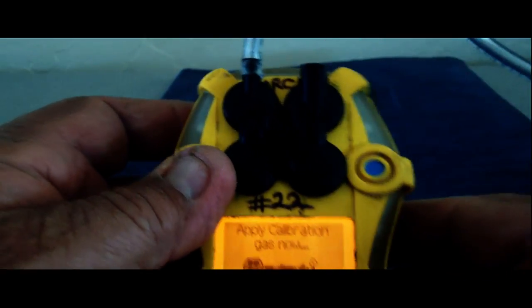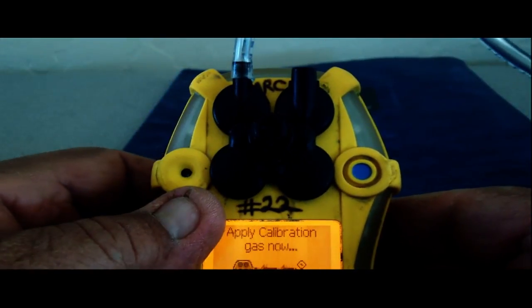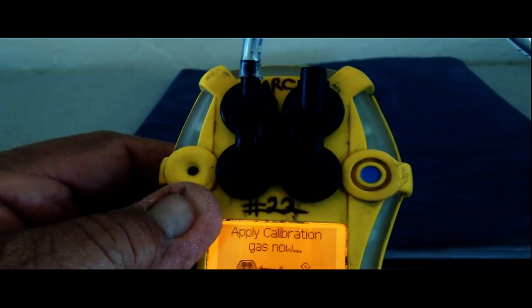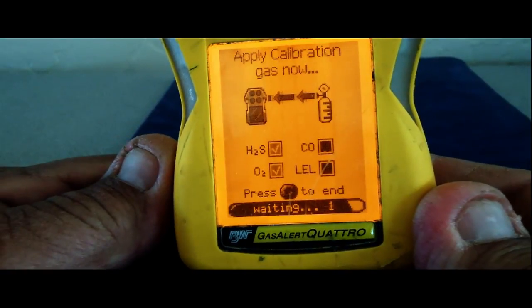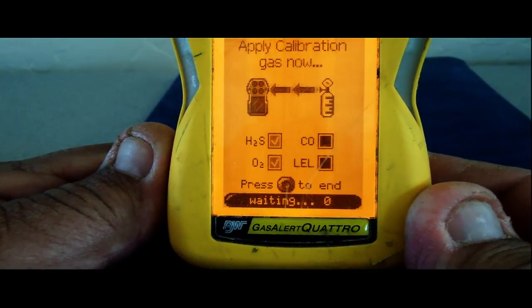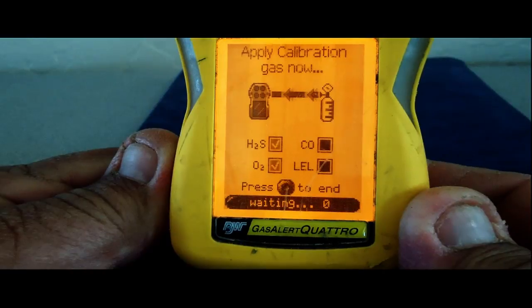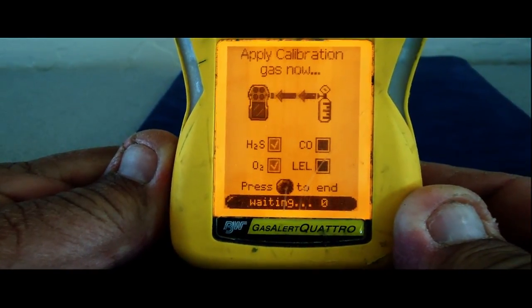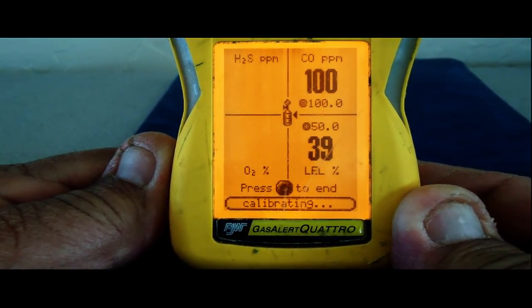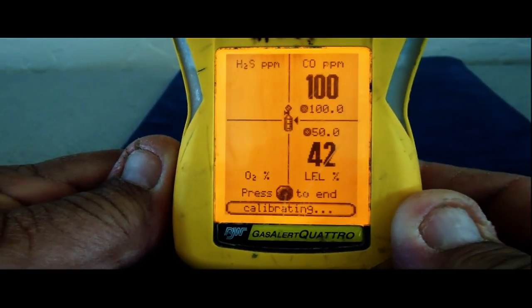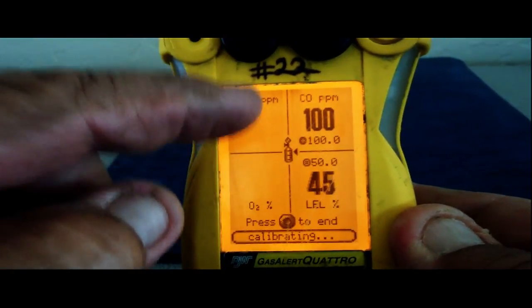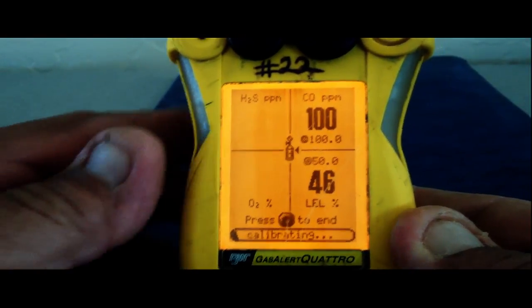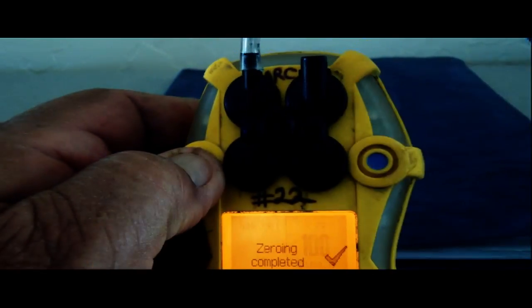There it is. When you're doing this, don't over tighten this little plastic thing. You can pull the nut through, or pull the little screw through the calibration cap. So I'm going to apply my gas. It gives me a little countdown. If you miss that countdown, you have to start the calibration process over. You see each of the sensors will darken as the meter picks it up. Yep, see, we missed it. It did not give us H2S, and it did not give us O2. So we're going to cancel that.